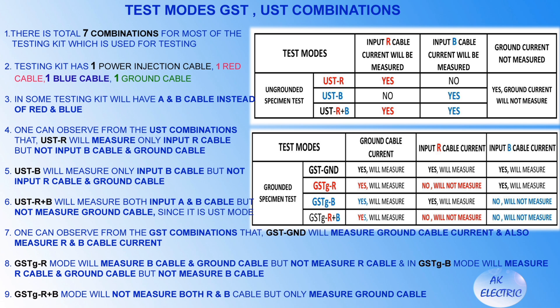In this slide we will see the test modes of GST and UST combinations. There are totally seven combinations from most testing kits used for testing purposes. The testing kit has one power cable injection, one red cable, one blue cable, and one ground cable. In some testing kits, A and B cables are used instead of red and blue cables. UST R will measure only the input red cable, but not the input blue cable and ground cable.